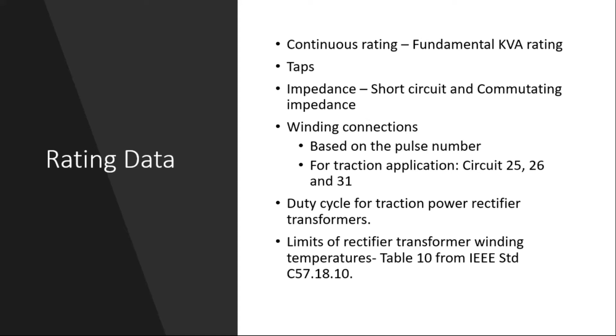Next, as we saw the duty cycle requirement in the traction, we will see in the next slide. The temperature limits for the traction application, or in general rectifier transformer, are given in table 10 of the standard. For example, if we have an industrial service requirement, then we have a special loading arrangement. When the load goes to an increased load, for example 200%, the winding temperature limit is 140 degrees Celsius. So those requirements are covered in table 10 of this standard.